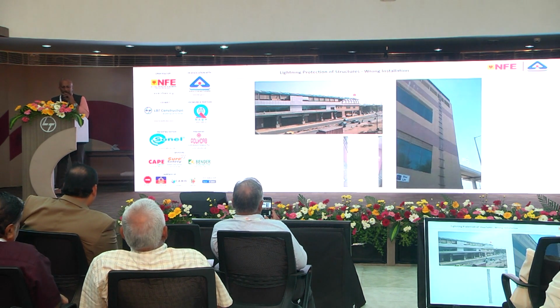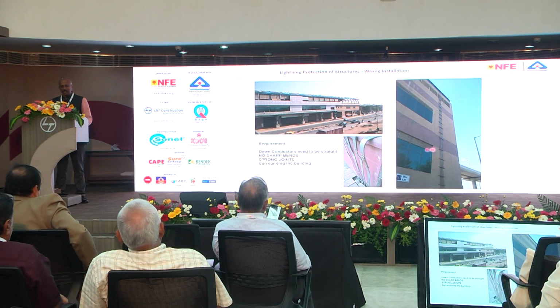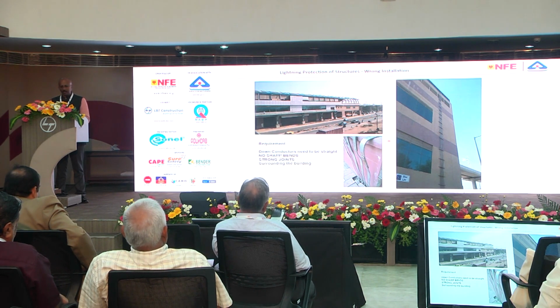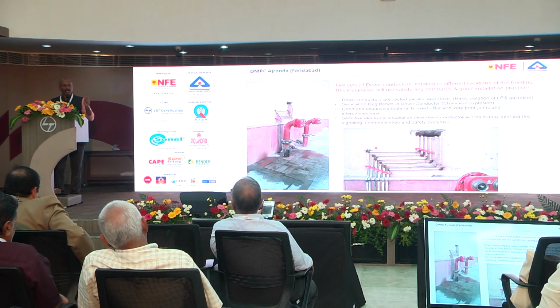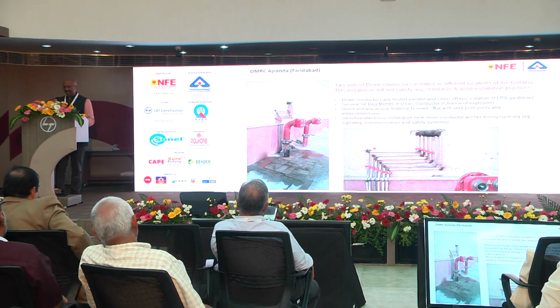Now, how the installations are carried out in India, you can find this kind of installation in several places, because the building is constructed, of course the tender is made along with the civil, but nobody took care of it, and later they wanted to install a lightning protection system. You can see all the down conductors are running through one side. See this, these are the down conductors. Nice installation. And the funny part is, this is a DMRC building. In the tender itself they have mentioned that all the lightning protection installation shall be aesthetically good. Aesthetically impressive. And this is the aesthetically impressive installation.